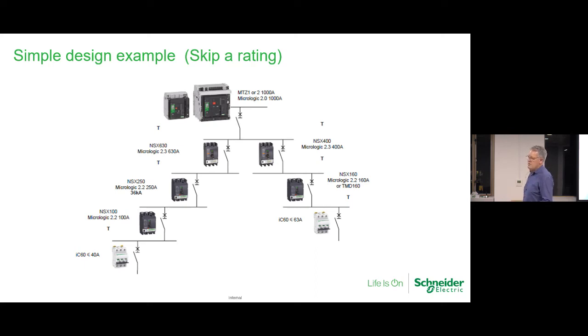So whenever I look at a consultant's drawing, it's so quick. It's not rocket science. If you just apply this straight away, you say, oh, it looks like there's an issue there. Why is that like that? Well, we've got no choice. I often heard that when I was seeing consultants occasionally: there's no way we can fix that. But there's always a way to fix something. You just have to have a look. Could be a trip, could be something else. Or maybe, as I said before, partial discrimination is acceptable, so you don't need to worry.